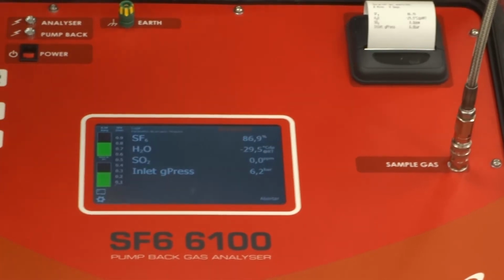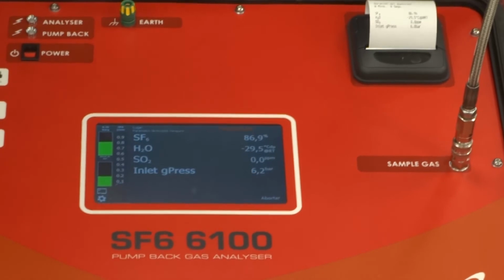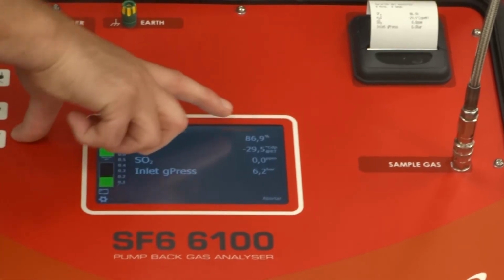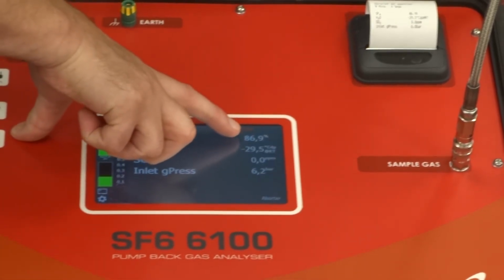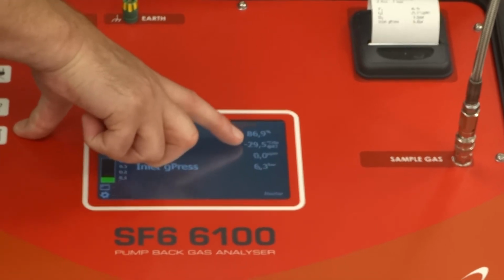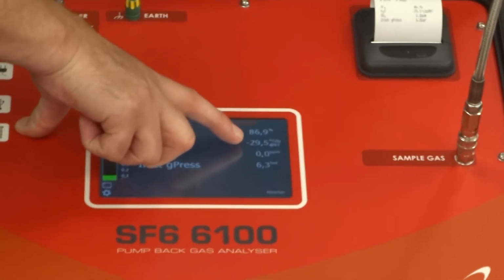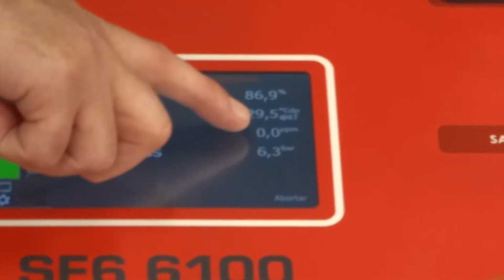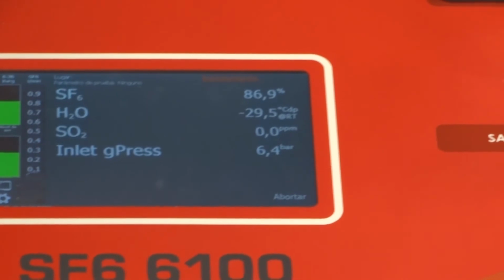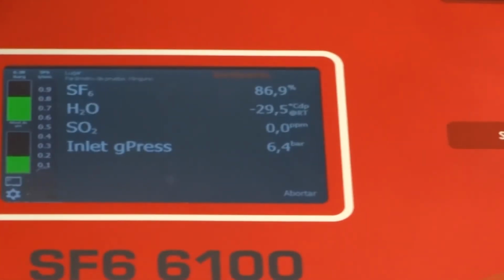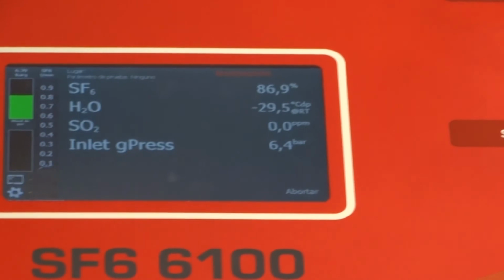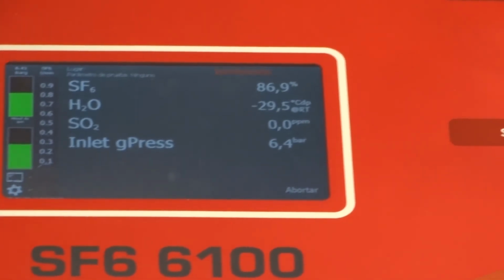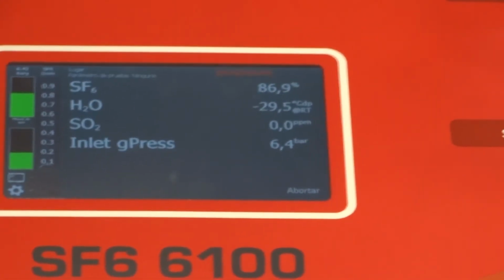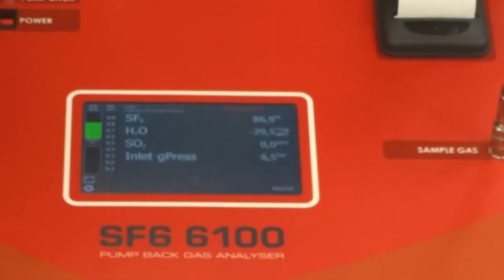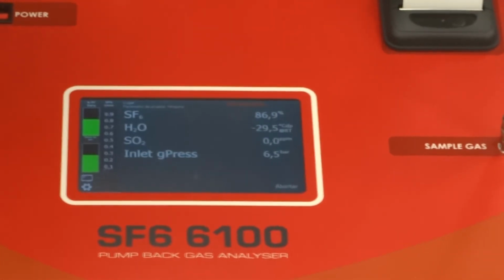So you can see this is a bottle of test gas that has just got some random SF6 value in it. So the result says that it's 87% SF6. The dew point is minus 25 CDP. The SO2 reading is 0 ppm, and the pressure is 6.4 bar. So we'll just let the pump complete its operation before I explain a few more features.